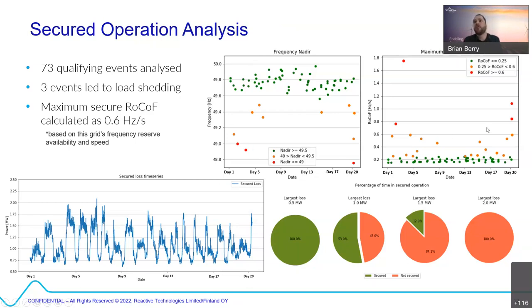When you plot them on RoCoF, you can see that if you have a RoCoF over 0.6 hertz per second, that's going to lead to under-frequency load shedding in this case. We did something a bit fancier than just looking at these charts, but that's essentially what we came down to: the secure RoCoF in this particular grid is 0.6 hertz per second. Bear in mind, that is based on this grid's frequency response, availability and speed. It might not be the same in your grid. So, turning this on its head, if we want to secure a RoCoF of 0.6 hertz per second, what is the maximum amount of power we can lose for a known inertia?